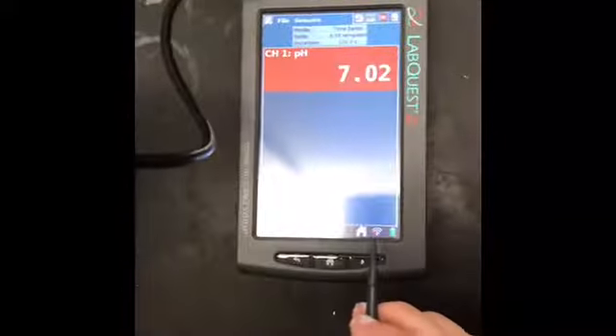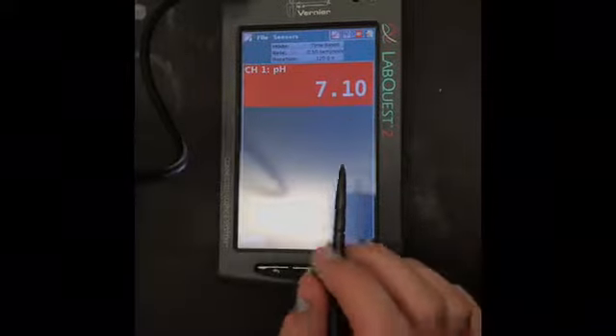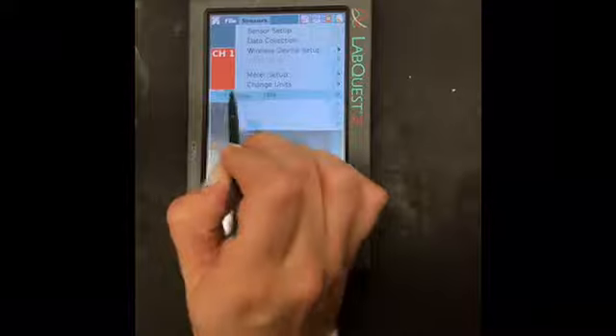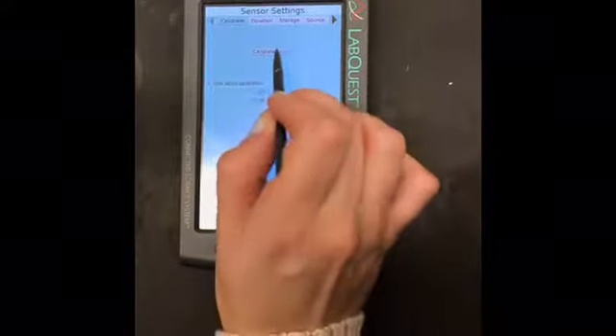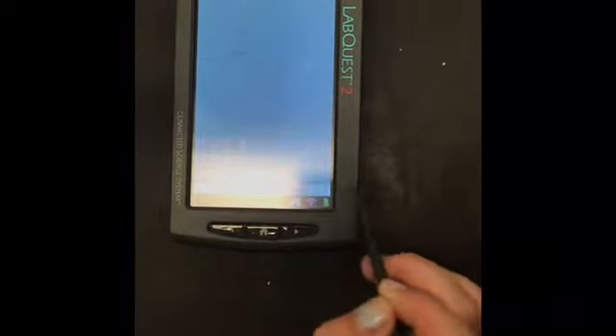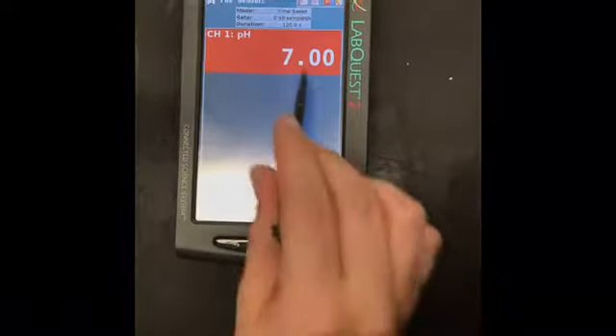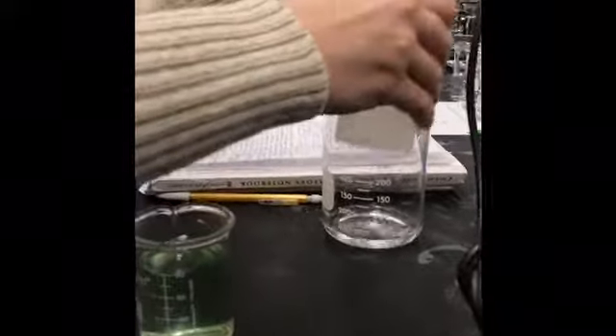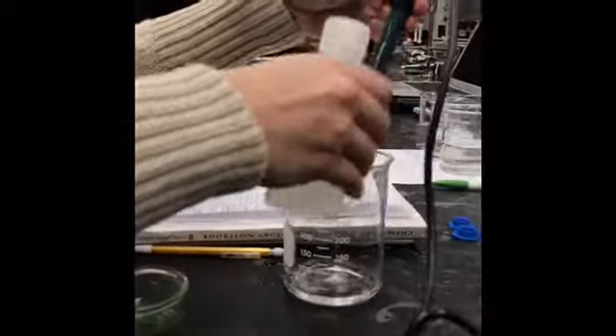To set up the meter, first hit the button called Sensors. Then, tap the word Calibrate, then CH1 pH. Tap 1 point calibration and calibrate now. Type in 7.0 for the pH of the buffer, and then hit Keep and OK, and you will see that the meter reading is 7.0 for the pH 7 buffer. Take the probe out of the buffer and rinse it with distilled water in a separate container.